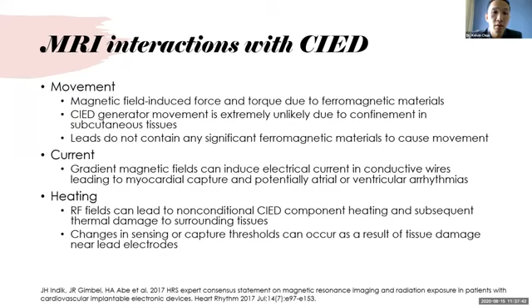Gradient magnetic fields can induce electrical current in conductive wires, leading to myocardial capture. And this can potentially lead to atrial or ventricular arrhythmias. Radio frequency fields can also lead to non-conditional device component heating and subsequent thermal damage to surrounding tissues, much like a focal ablation. This local tissue thermal damage can also lead to changes in sensing or capture thresholds.